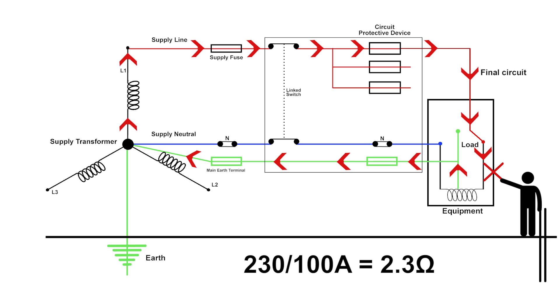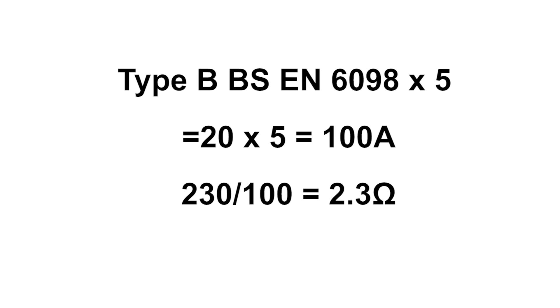We need to make sure that our earth loop path for this particular device, when our cable is operating at 70 degrees, is 2.3 ohms maximum. As I said, any type B protective device has to operate within 0.1 of a second at a maximum of five times its rating. We're using a 20 amp device, so if we multiply that by five, it means that when 100 amps flows through it, it must operate within 0.1 of a second. Clearly, for 100 amps to flow, if I just use Ohm's law—230, which is my voltage, divided by 100—tells me that I've got a value of resistance of a maximum of 2.3.